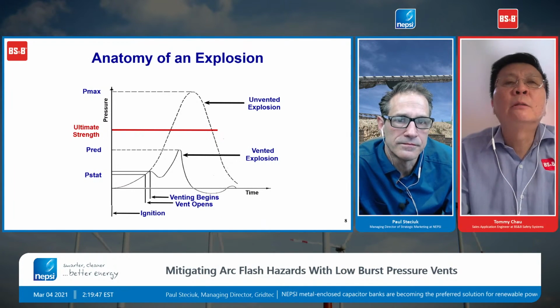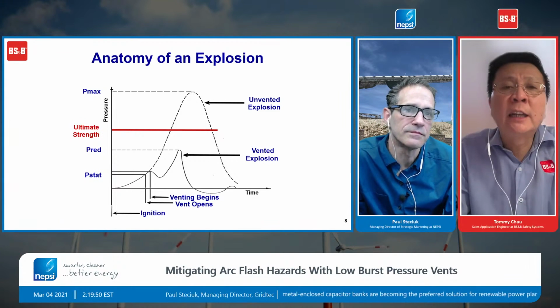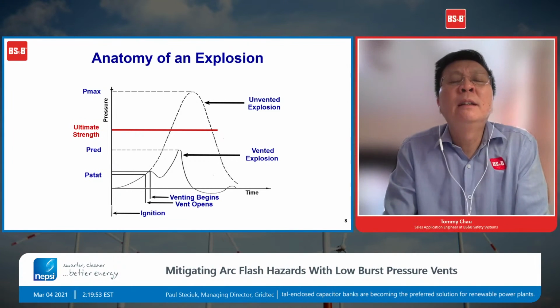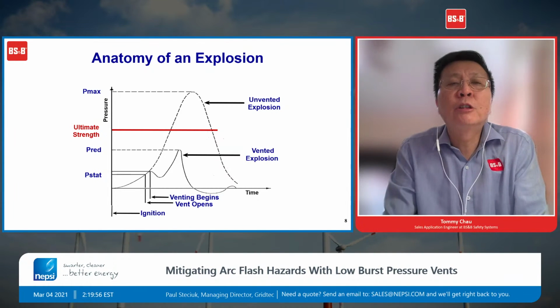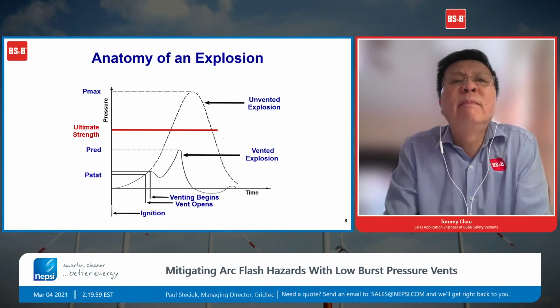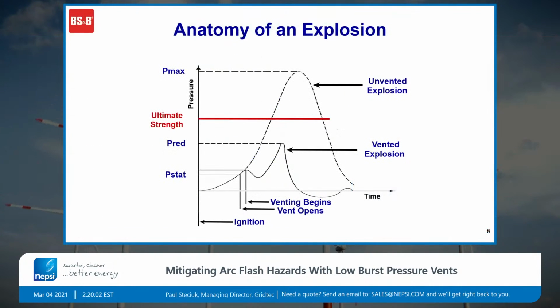Yeah. So again, the very first thing that can happen is you have some type of ignition. And the very next thing is the burst pressure on the explosion panel, the explosion vent, to open. And then the earliest comment on the P-red, so that would be 2/3 of the ultimate strength. So you want to design the explosion vent below the P-red, and then you have the very top, the Pmax value that we mentioned earlier. So the Pmax could be up to 8 to 10 bars sometimes. So you could see up to about 150 psi on the Pmax on the product. On some material, yeah.